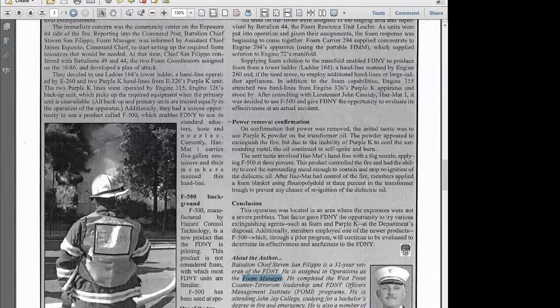So the transformer caught on fire. They used 1,500 pounds of purple K dry powder that just pissed off the fire. When that's not working, the next natural reaction we see fire departments do is start a foam operation. So they started a foam operation, applied foam for about an hour. Of course, it didn't put the fire out because the transformers are 3-dimensional. The foam just rolled off the top of the transformer down into the Bronx River, which caused a hazmat issue, because now we have foam going down into the Bronx River, leading to an environmental issue.